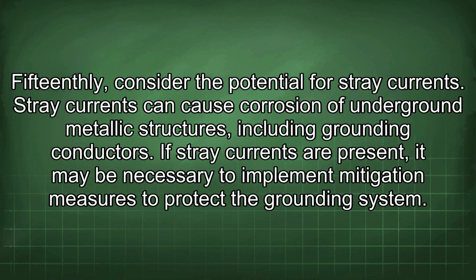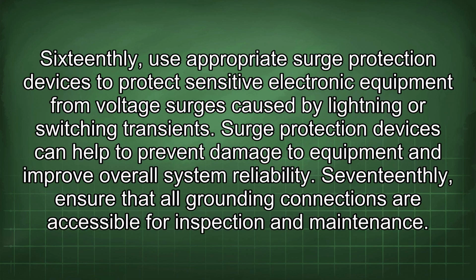15thly, consider the potential for stray currents. Stray currents can cause corrosion of underground metallic structures, including grounding conductors. If stray currents are present, it may be necessary to implement mitigation measures to protect the grounding system. 16thly, use appropriate surge protection devices to protect sensitive electronic equipment from voltage surges caused by lightning or switching transients. Surge protection devices can help to prevent damage to equipment and improve overall system reliability.